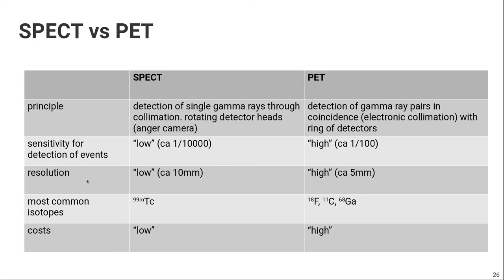In terms of resolution, if we look at standard whole body scanners as used in a typical hospital, we also see that the resolution of the reconstructed images is way higher in PET. In modern PET scanners, that's around 5 millimeters now. In modern SPECT scanners, that depends a bit on the SPECT system and especially on the collimator that you use. But the typical benchmark right now is around 10 millimeters. So the resolution of the PET images is usually way higher than the resolution of SPECT images in whole body human imaging.